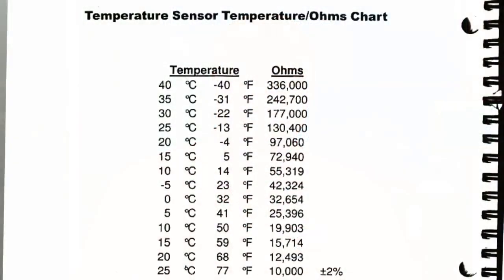The other thing you can do, if you're worried about it and think the thermistors might be off, is that the only way you can really check thermistors is to ohm them out. The best way to ohm out a thermistor, in my opinion, is to drop it in a cup of ice water, and then you get the known ohm value. All of our defrost sensors that we're using in our regular heat pumps have the same resistance value. So at 32 degrees, which is what the ice water is going to be, you would be at 32,654 ohms. If you took the ambient sensor off of the heat pump we're talking about and dropped it in a cup of ice water, you should read 32,654 ohms. If you're off plus or minus about 500, you should still be okay.